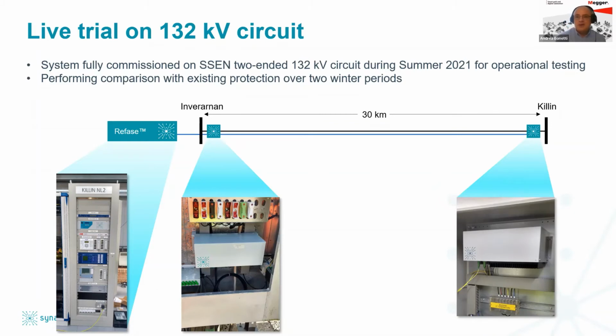We really tried to do a lot of tests to make this fail, because we wanted to make sure we tried every possible scenario: full load from left to right, sudden bolt into the left, the reverse, high load reverse, and low load reverse. We tried all the most difficult tests we could manage to do, but it was working fine, I have to say. Impressively working fine.